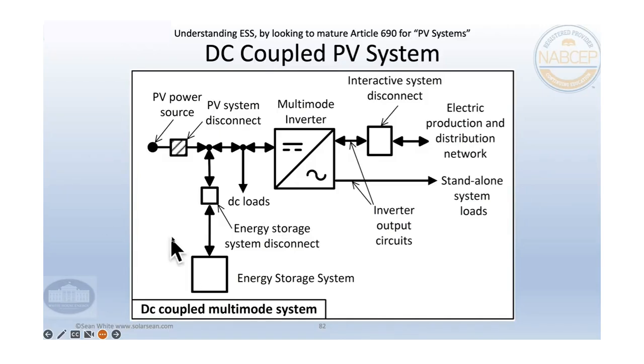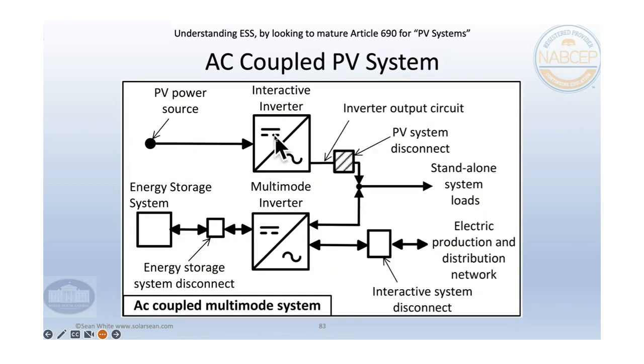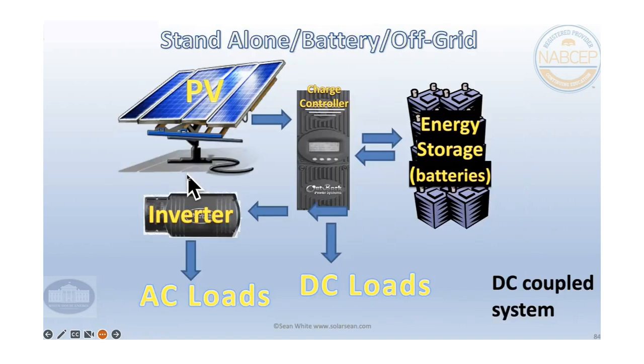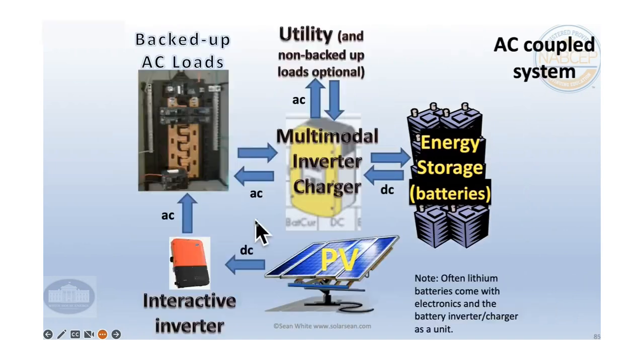Kind of convenient. This is just a diagram from the NEC that you've probably seen a million times, but it kind of gives us an idea. The PV system disconnect is where you separate PV from any other system, such as energy storage or loads. So here, with a DC coupled system, your DC disconnect is going to be your PV system disconnect. Whereas with an AC coupled system, you have an interactive inverter, and your inverter is only there for PV. So then here is your PV system disconnect. There's an AC disconnect. There's the energy storage system. They took these images in the 2023 NEC and moved them to 705 and changed them around a bit. So there's some DC coupling, there's some AC coupling. You have an interactive inverter. You're tricking it into thinking that there's a grid, or it's a microgrid with energy storage.